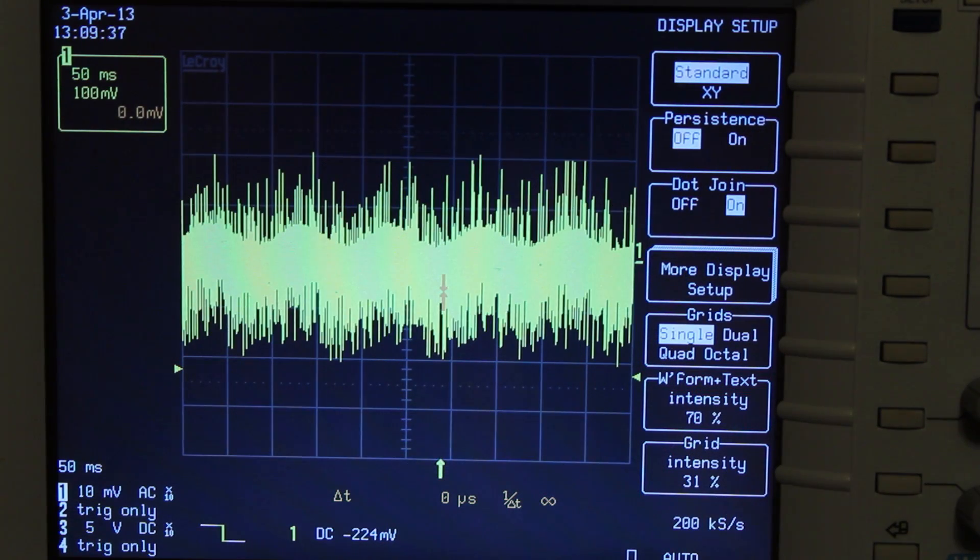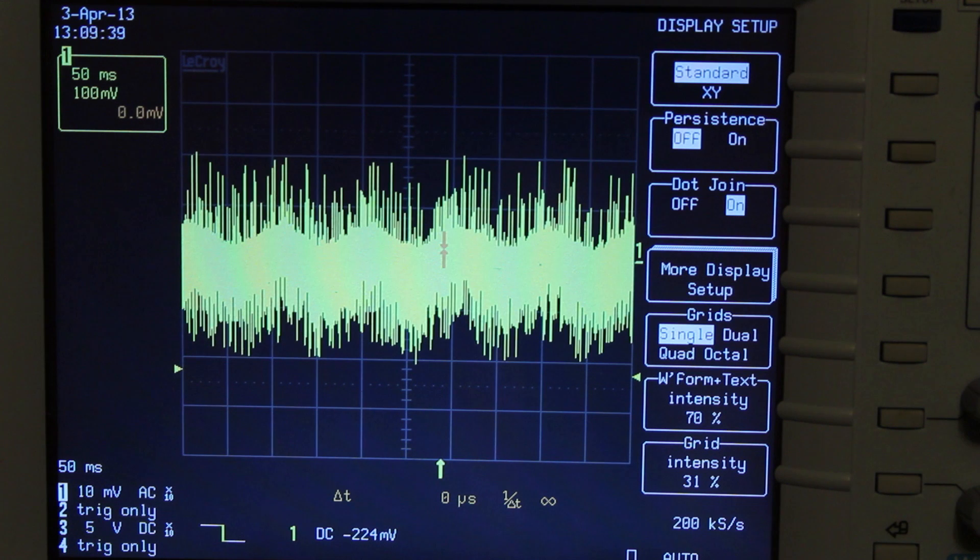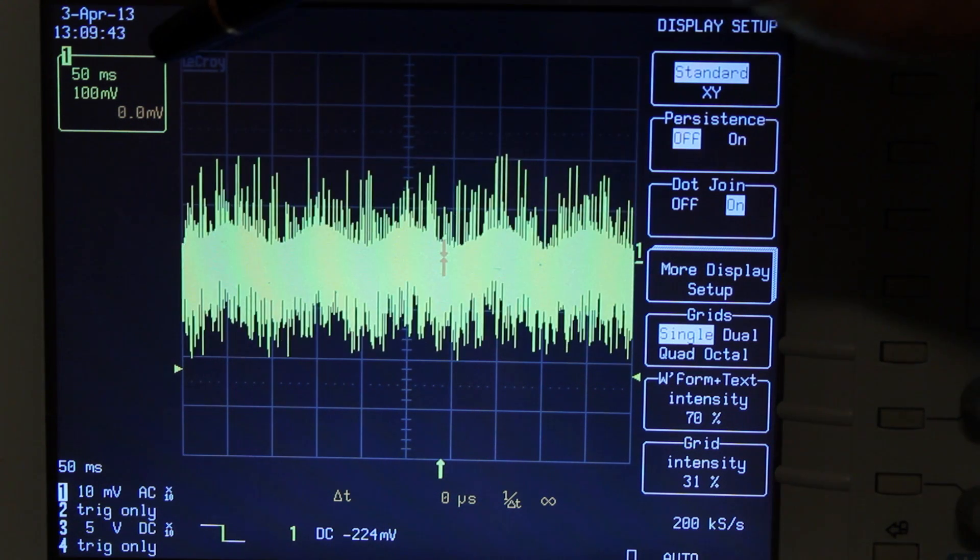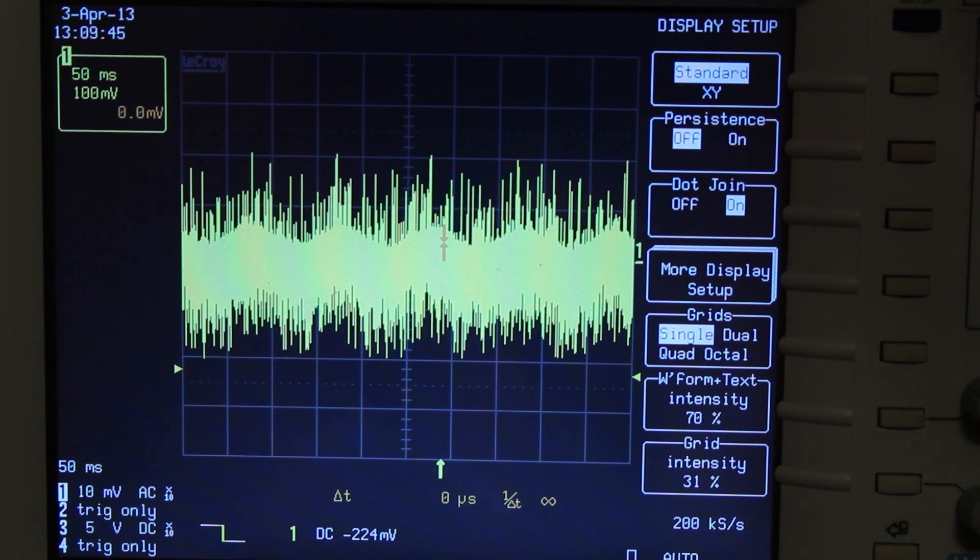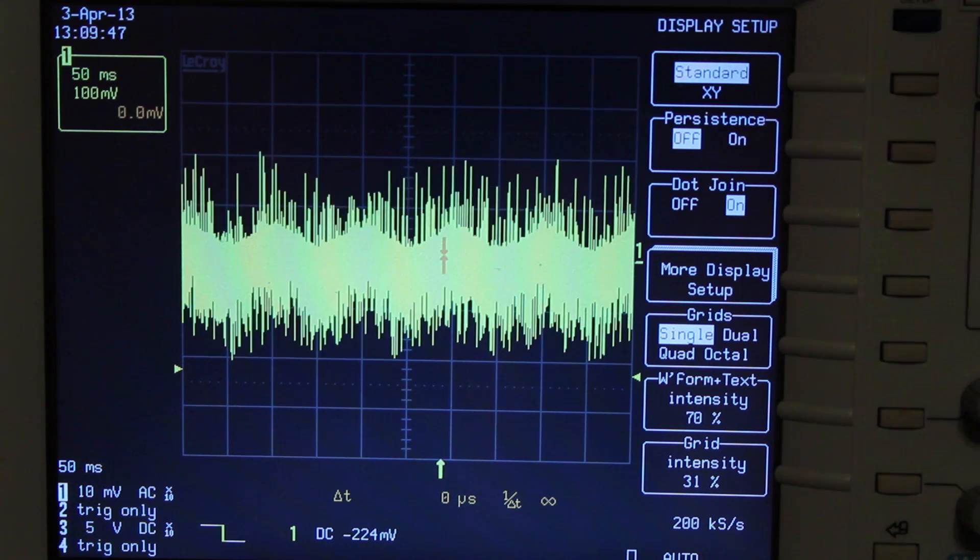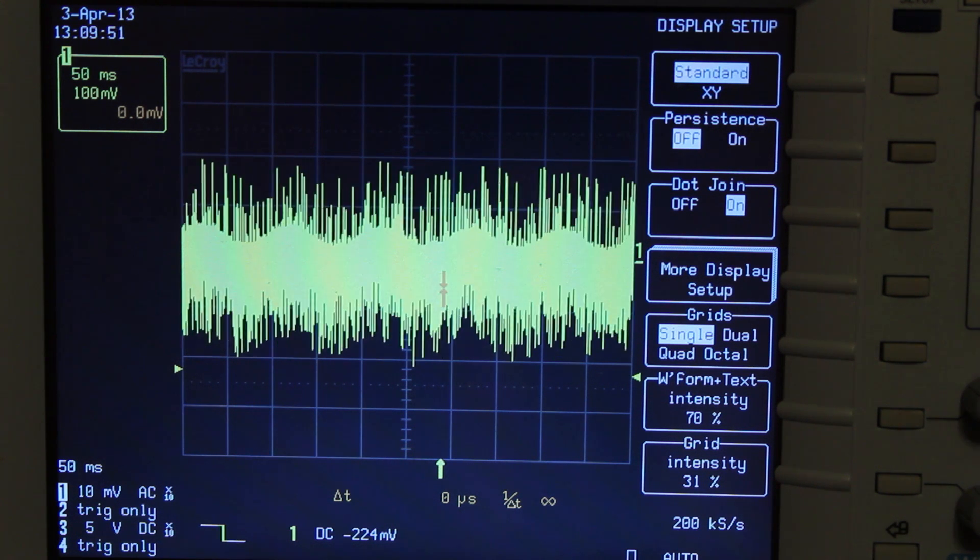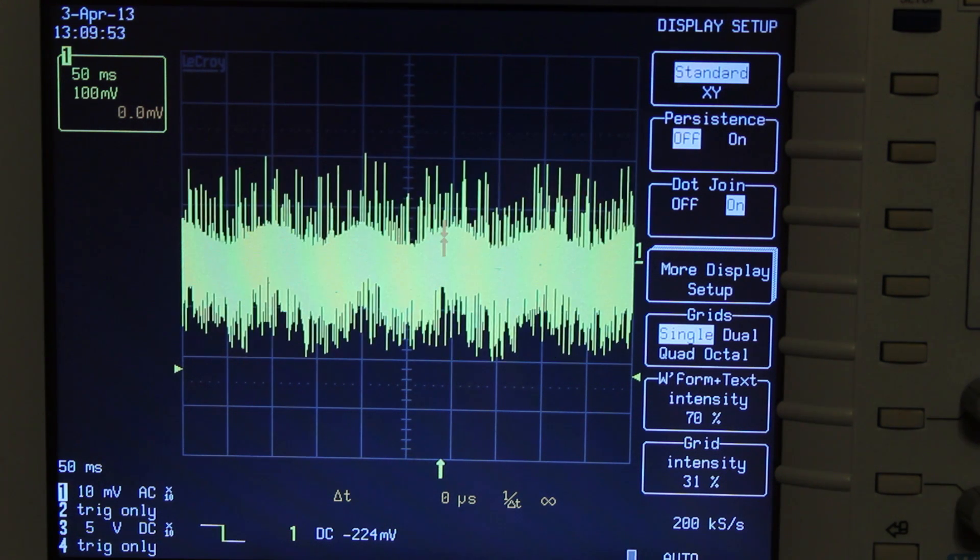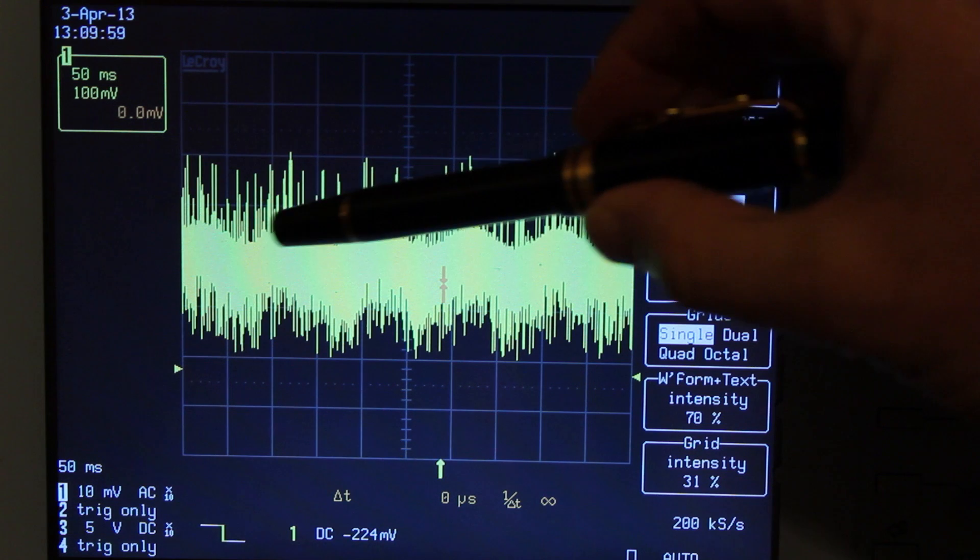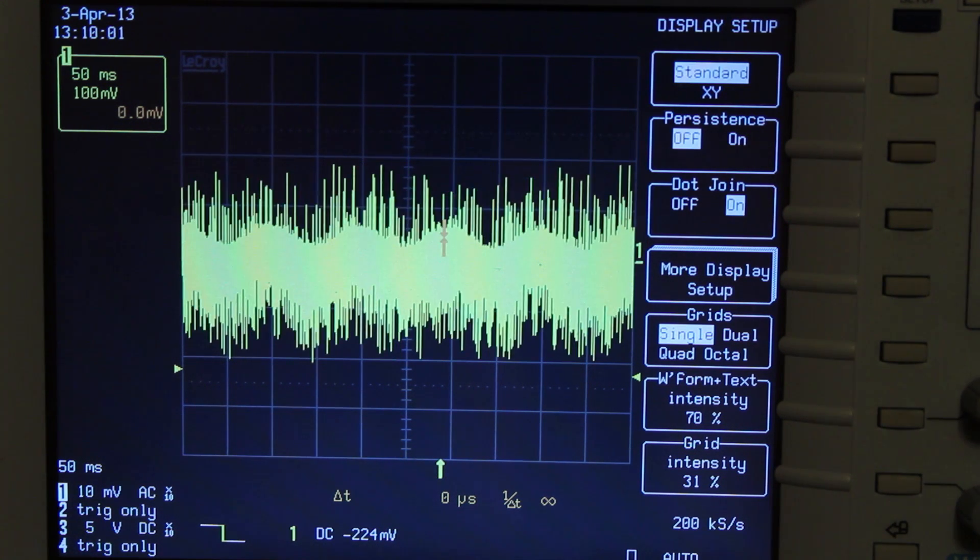Right now what we're looking at on the oscilloscope is the output voltage of a power supply. The scale right here you can see is 50 milliseconds per division and 100 millivolts per division. As you see from the traces here, we've got lots of things going on all at the same time. Along the top of the trace here, you can see a 10 hertz modulation envelope, which is something we're going to have to measure.